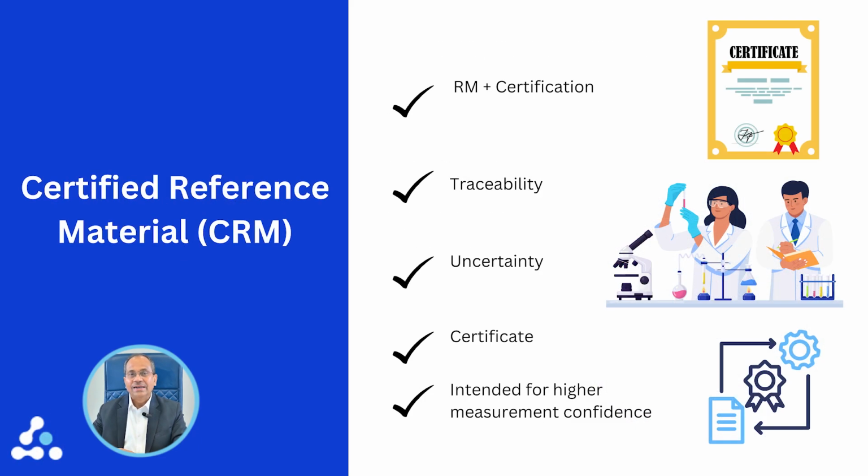On the other hand, a certified reference material or CRM goes a step further. Its value is not just known, it is scientifically established with traceability, defined uncertainty and certification. This makes it a reliable and defensible benchmark, particularly in applications where confidence in measurement is essential. This is especially relevant in regulated and high precision analytical work.